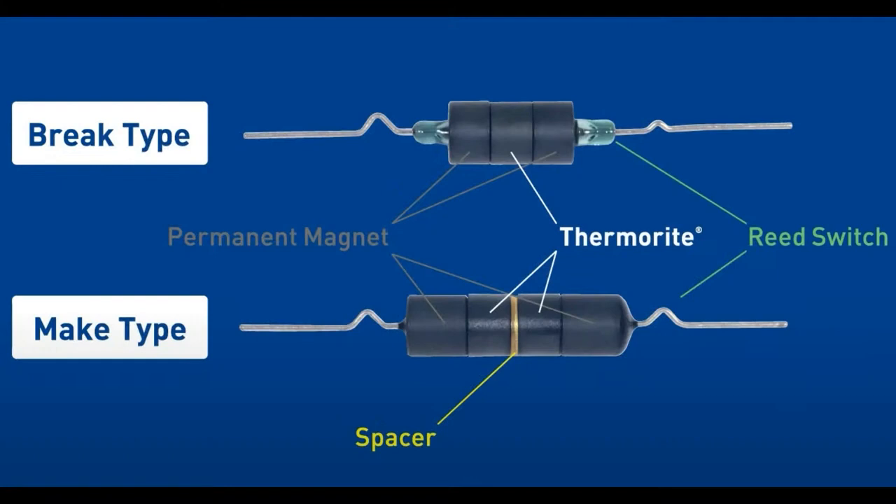So there are two types. They do a thing where the outer ring is the thermorite — that material is a magnet until the temperature rises to a certain point, and then it becomes demagnetized. For the break type, the thermorite is in the middle with a permanent magnet on the outside. For the make type, the thermorite is in the center with a little spacer. In the center is a normal reed switch.